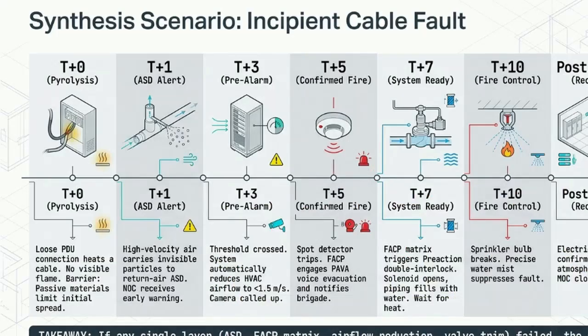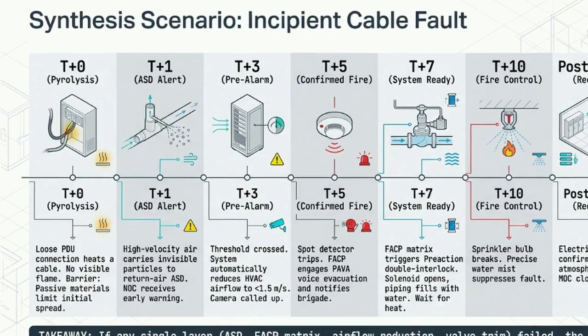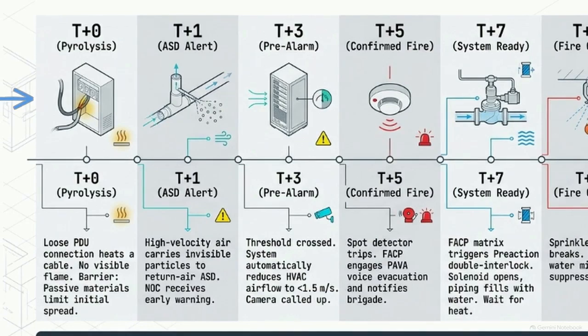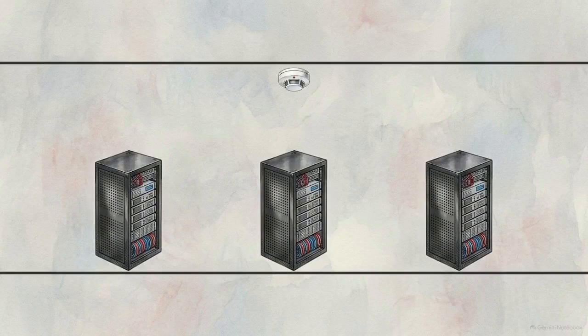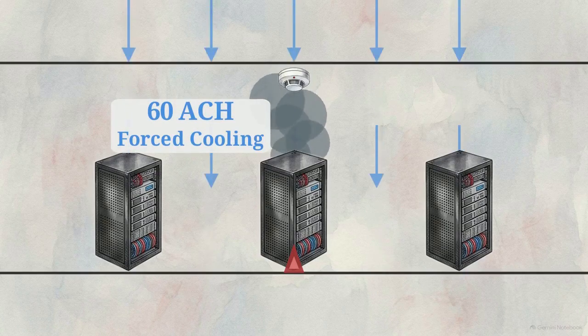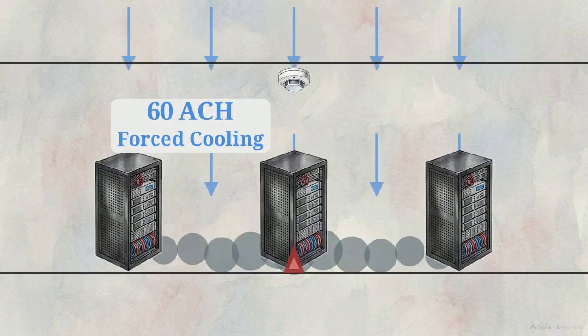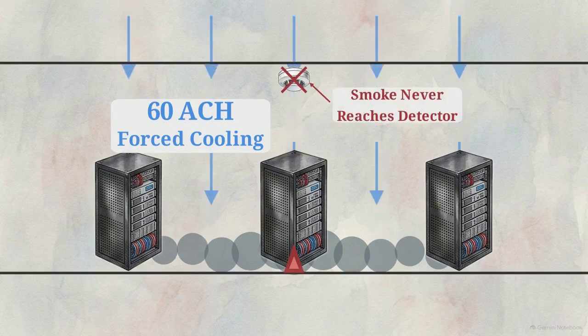We can deconstruct how these layers coordinate by following the timeline of an incipient cable fault inside a high airflow data hall. At T+0, a loose PDU connection begins heating a cable. This pyrolysis produces invisible particulate matter long before an open flame appears. Traditional ceiling-mounted spot detectors are ineffective in this specific environment. Extreme cooling forces alter the basic physics of a fire. 60 air changes per hour of cold supply air will force a thermal smoke plume downward, flattening it and preventing it from reaching the ceiling.